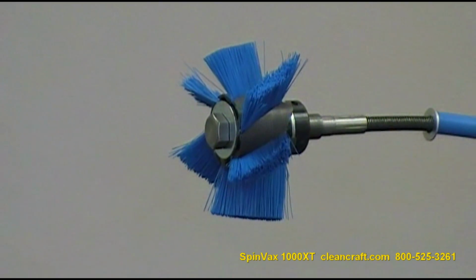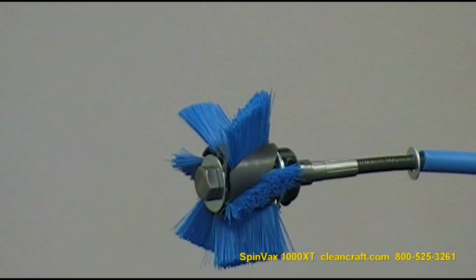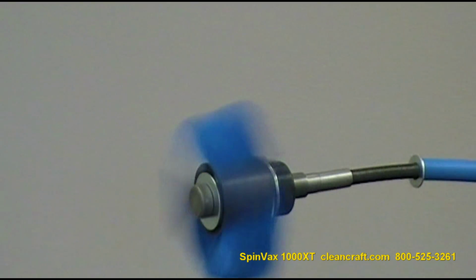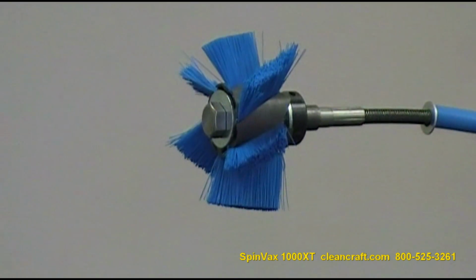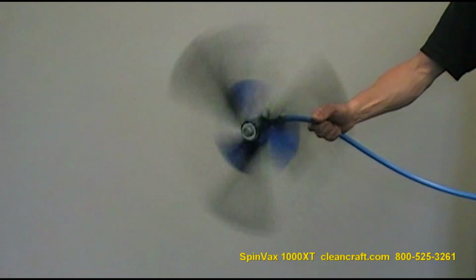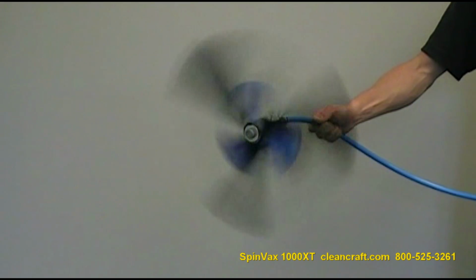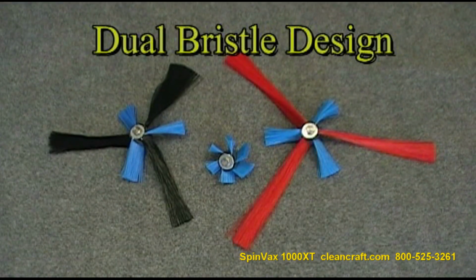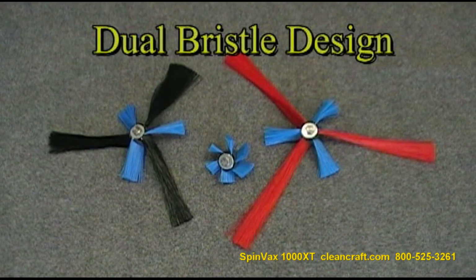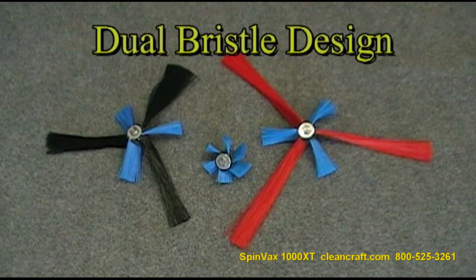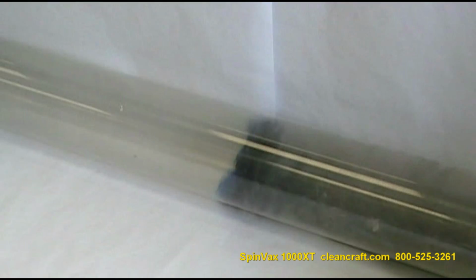These brushes have precision angled brush alignment to create a reverse sweeping action to improve the debris removal and extraction process. These FlexStend brushes automatically self-adjust to the proper size of the duct. Plus, the dual bristle design on the standard and large brushes helps stabilize the positioning of the brush throughout the duct. As you can see in this clear duct, the standard size brush automatically adjusts to the size of the duct being cleaned. Notice the reverse sweeping action carry the dirt and debris back toward the vacuum hose.